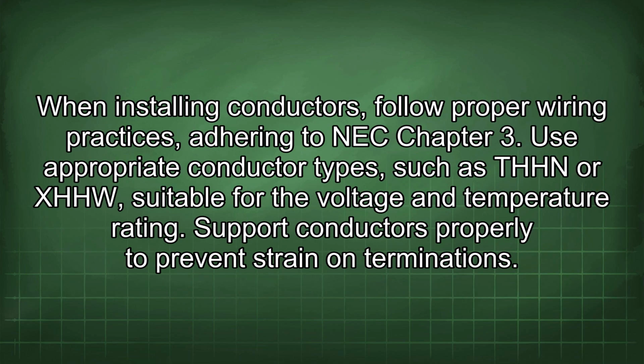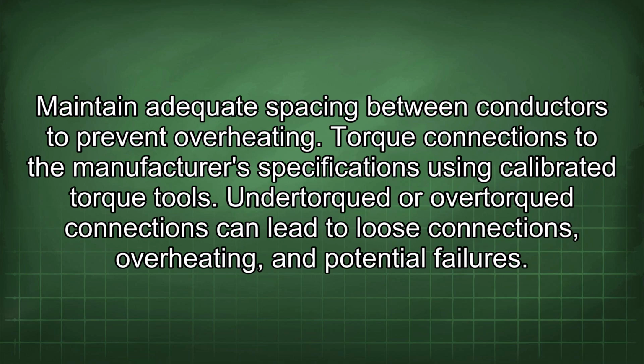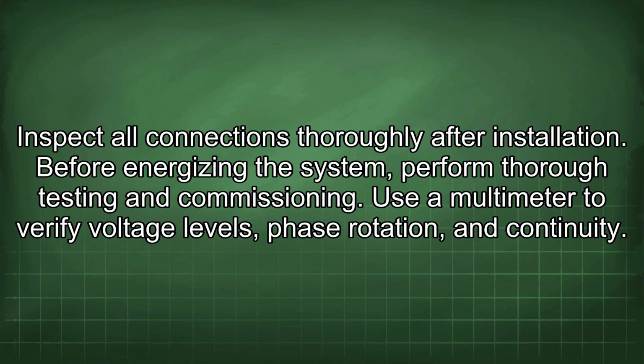When installing conductors, follow proper wiring practices, adhering to NEC Chapter 3. Use appropriate conductor types, such as THHN or XHHW, suitable for the voltage and temperature rating. Support conductors properly to prevent strain on terminations. Maintain adequate spacing between conductors to prevent overheating. Torque connections to the manufacturer's specifications using calibrated torque tools. Under-torqued or over-torqued connections can lead to loose connections, overheating, and potential failures. Inspect all connections thoroughly after installation.